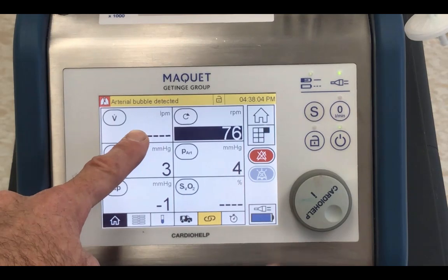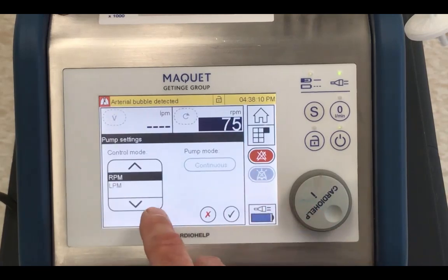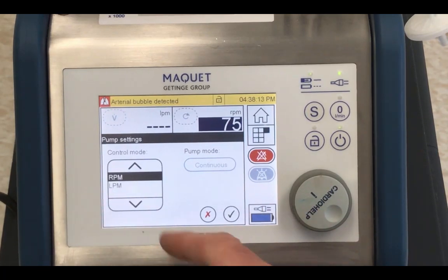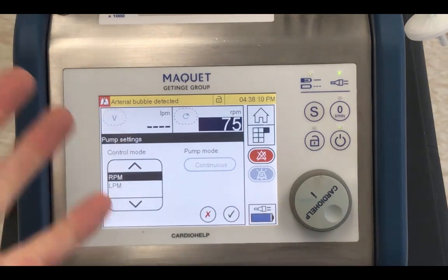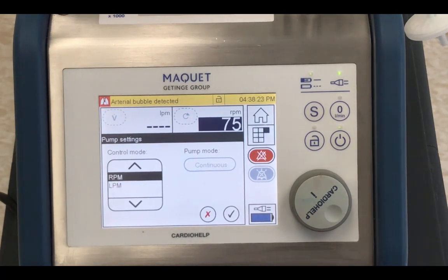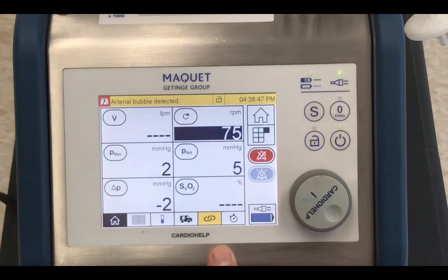In my experience, it's not super popular or common for programs to run in the LPM mode. If you're doing veno-venous ECMO, it would probably have very little impact unless somebody were kinking the lines or you had significant preload problems. It's hard to get an afterload problem without a kinked line in VV ECMO. If you were doing veno-arterial ECMO, however, if you were in LPM mode, then as the patient's blood pressure changes throughout the day, you would maintain a steady flow. But in my experience, most centers run in RPM mode, so we're going to leave that in RPM mode. And we're going to get out of this menu by pressing the green check mark here. That's going to enter the data.